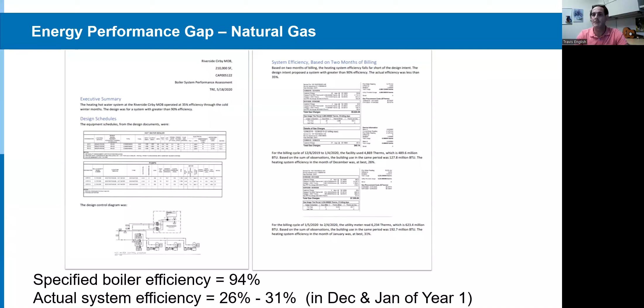The other thing we've learned is that the units used in energy modeling are often terrible. We usually talk about it in kBTU per year, which isn't very useful. It's better in kBTU per month, and even better in BTU or watts per hour. So during design we always ask the team to publish the full 8,760 hour model, so we can see fan power, cooling power, and other loads by the hour. That's what we validate during commissioning with our acceptance criteria.